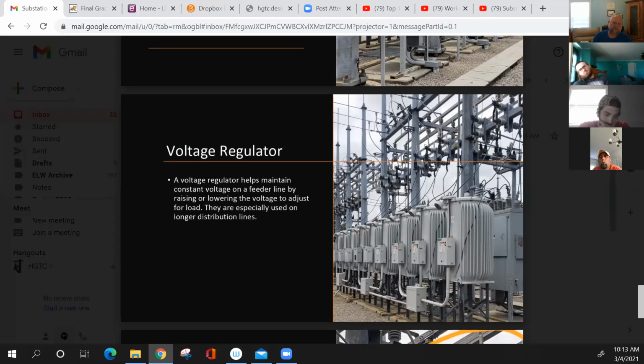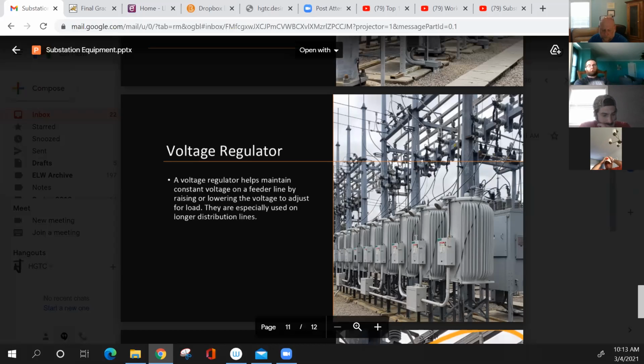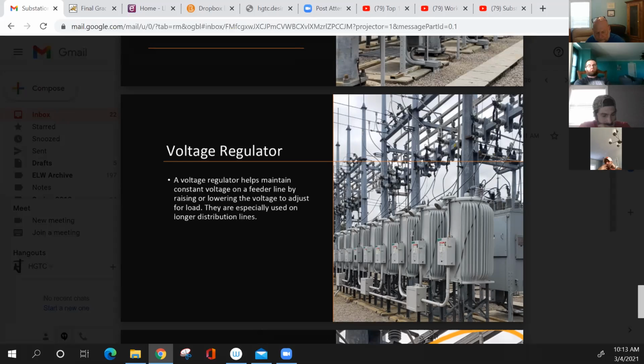Had a few instances where snakes would get into a substation, climb up on the breaker, and take the whole sub out. Any fault that I had in there from that bus side back to the transformer, it would open up the high side switch and take that sub out. So I think this is a pretty good way to build them with the voltage regulators beyond the breaker. So 3 voltage regulators, and that's a way.